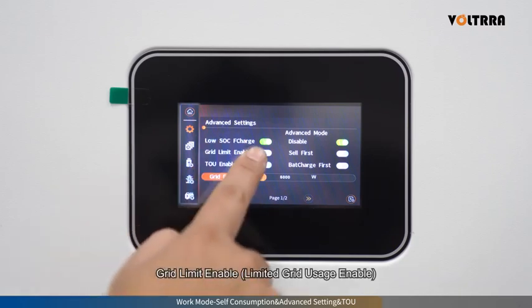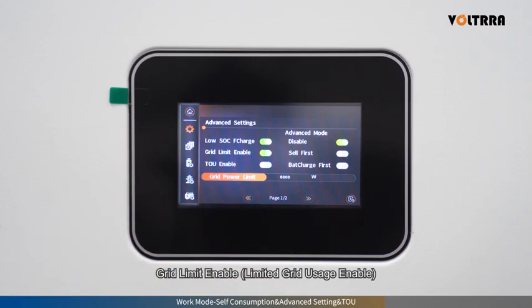Grid Limit Enable, Limited Grid Usage Enable. PV Power Priority: Load, Battery, Grid. Load Supply Priority: PV, Grid, Limited Battery. PV energy is prioritized for supplying the load. When PV generation is sufficient and exceeds the load demand, the surplus PV power charges the battery. When PV generation is insufficient and lower than the load demand, the load will preferentially draw power from the grid.